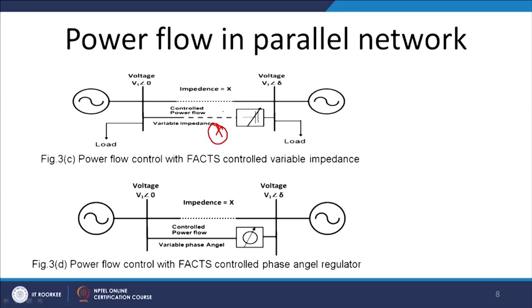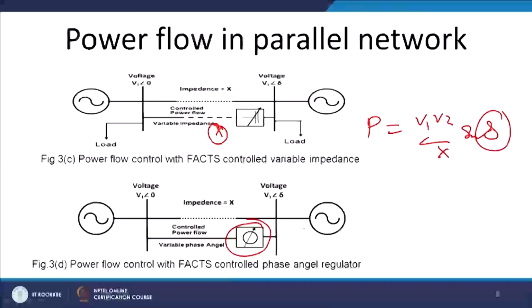as governed by the authorities. Now in the same way, instead of controlling the impedance, as we know that P equals V1 V2 by X into sine delta, we can change delta, and this is called a power angle regulator. This works better when the power angle is very low, less than 30 degrees or so. Then by changing delta, we also control the power flow x through this FACTS control line, and ultimately the other part will carry 1 minus x amount of the controlled power.